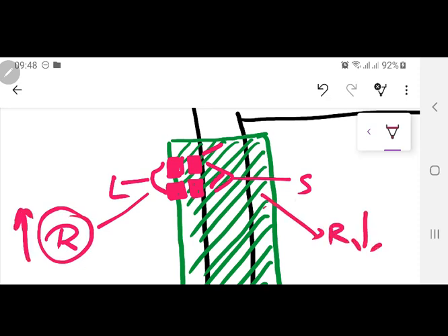When you have four parallel wires with two wires having a larger resistance and two wires having a smaller resistance, current will always take the least resistance path. So there will be unequal balancing on the four wires over here. Now this is a very problematic thing, because near the core the resistance is small, so there is more current. More current means more current density. More current density means it's going to heat up more. More heat means that the core is also going to heat up more.